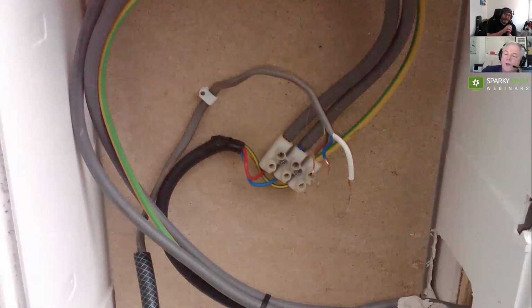And that does mean that through this connection onto that 2.5 mil, there will be some heat generated at that connection. This is obviously combustible material that this is mounted onto, it's fixed onto chipboard. So that was kind of our conclusion, that this is going to be quite a warm connection. Even though the cable there is huge, the smaller cable it's going onto will get warm, that connection will get warm, and it's just not a suitable connection.